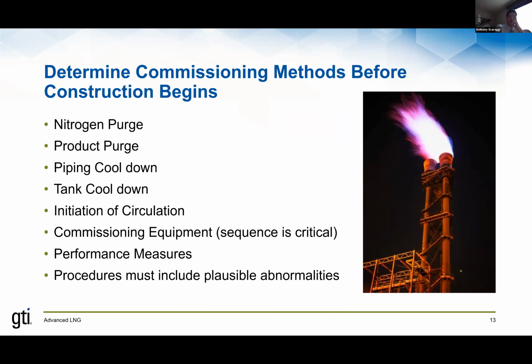Commissioning is a huge part of building a facility, putting a facility into service. The things you have to consider for commissioning are things like your nitrogen purge. How are you going to purge the equipment to remove moisture, to remove oxygen from the systems, to eliminate the hazard of possibly having a combustible mixture during startup? You can do a nitrogen purge. You can then purge with the product itself, meaning purge with a refrigerant or natural gas vapors. These are all considerations in commissioning.